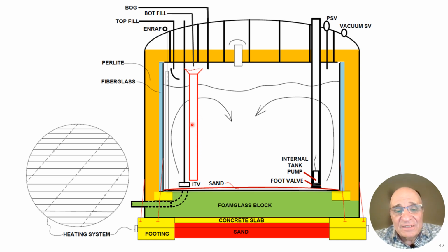Well, light LNG means there's a very light, low density head here, low density fluid in here, which causes a higher head required to get to the same pressure as the liquid that's out here. So you can have, let's say, a liquid that's up at this point here, giving you the same pressure as a liquid that's over here. And this could be as much as a 5-foot difference. So what happens as this liquid level gets higher, this funnel starts to overflow and you're really doing a top fill at the last stage of your filling of the tank when you want to be doing a bottom fill.